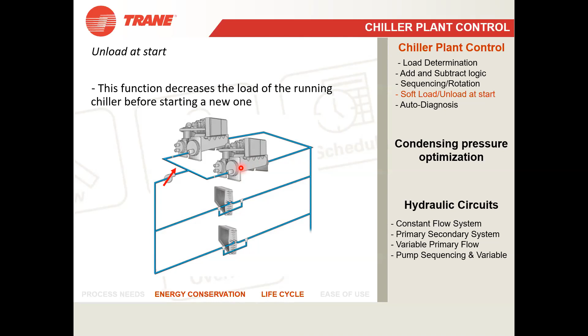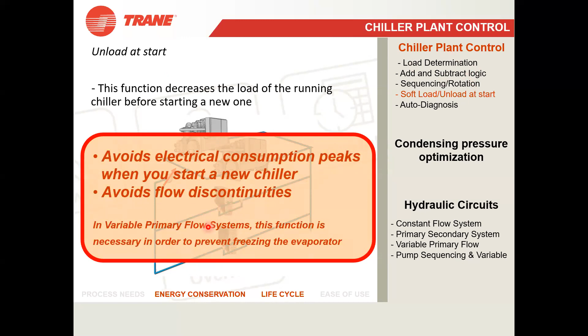Here I have shown that both are primary pumps, right? In a variable primary pumping flow system, if flow discontinuity happens, there is a chance that due to very, very low flow, the water may freeze at the evaporator coil. And if the evaporator coil freezes, it will be damaged, or you have to clean it completely, which means maintenance, major repair, major money loss. The commercial expenditure is also very huge. So one more feature is that this CPC, with unload at start, will help you maintain that flow never gets discontinued from any chiller.